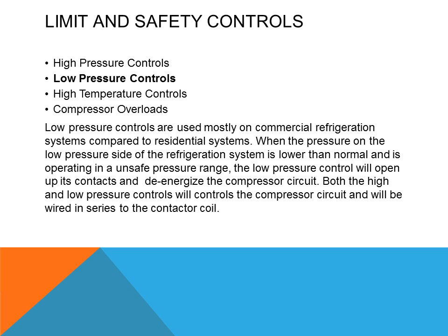Low pressure controls are used mostly also on commercial refrigeration systems compared to residential refrigeration systems. When the pressure on the low pressure side of the refrigeration system is lower than normal and is operating in an unsafe pressure range, the low pressure control will open up its contacts and de-energize the compressor circuit also. Both the high and low pressure controls will control the compressor circuit and will be wired in series to the contactor for the compressor.